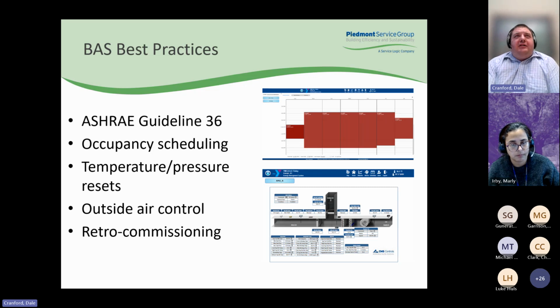Another BAS best practice that is a good low-cost thing to do is retro-commission your buildings. Over time, we know our buildings drift a lot from their original intended control sequences and where they were originally commissioned, as people operate the buildings over time. So going back and verifying the systems are operating as they should be, and trying to make sure that there aren't overrides in place and things that may be keeping you from optimizing your energy efficiency.